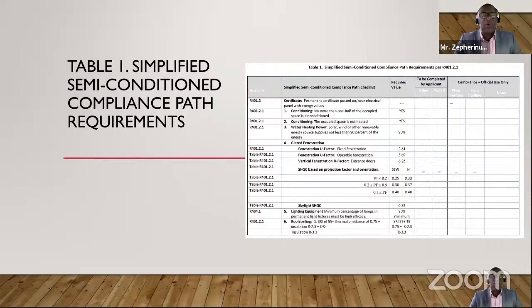When it comes to the solar heat gain coefficient, it considers 2 things. It considers the orientation. Is the window or door located on the south, east, or western side of the building? The 3 facades, south, east, and west, would be exposed to more sunlight, so they get more stringent measures for the solar heat gain coefficient, as opposed to the northern facade. So most architects would use the northern facade to have more natural light and include more fenestration on the northern facade of buildings. So these would be the requirements for skylights as well, the solar heat gain coefficient, and you follow this table to demonstrate compliance with the code.